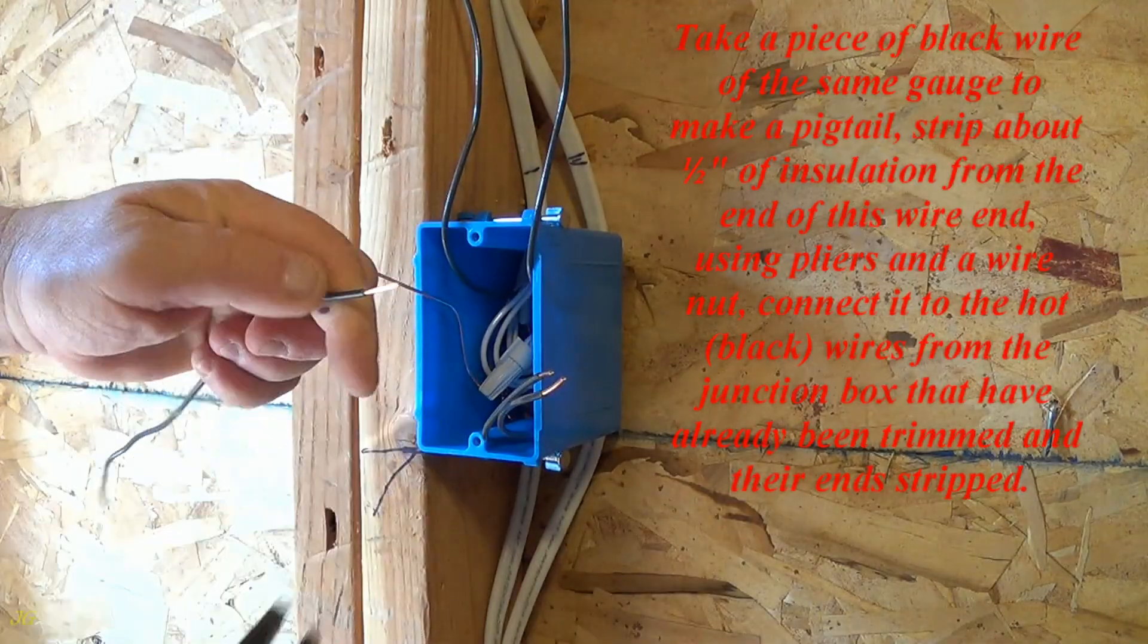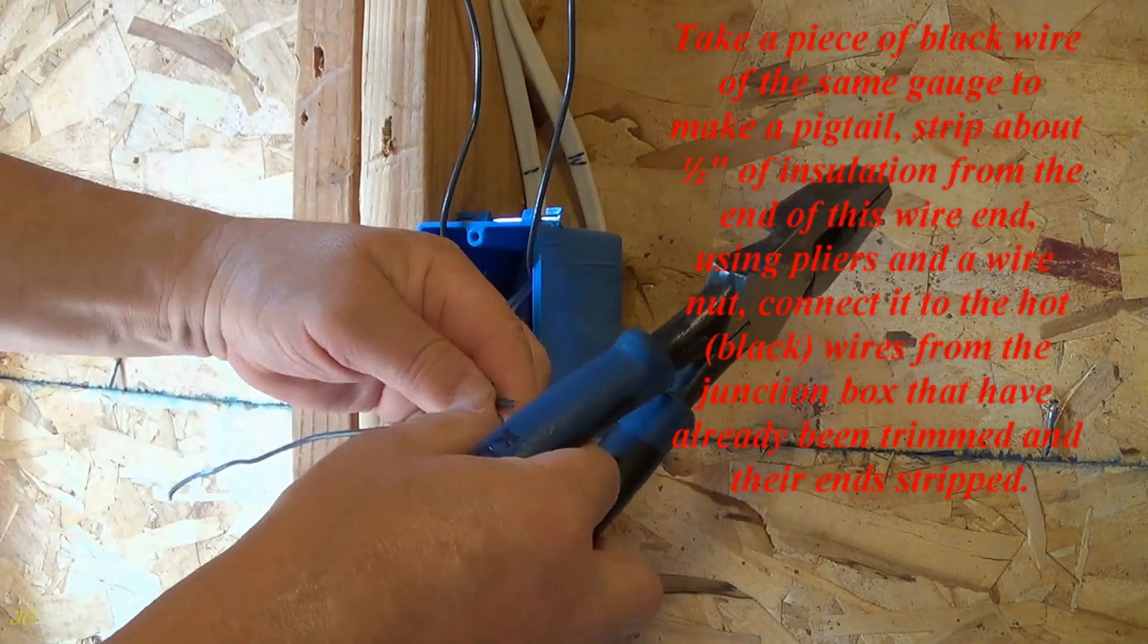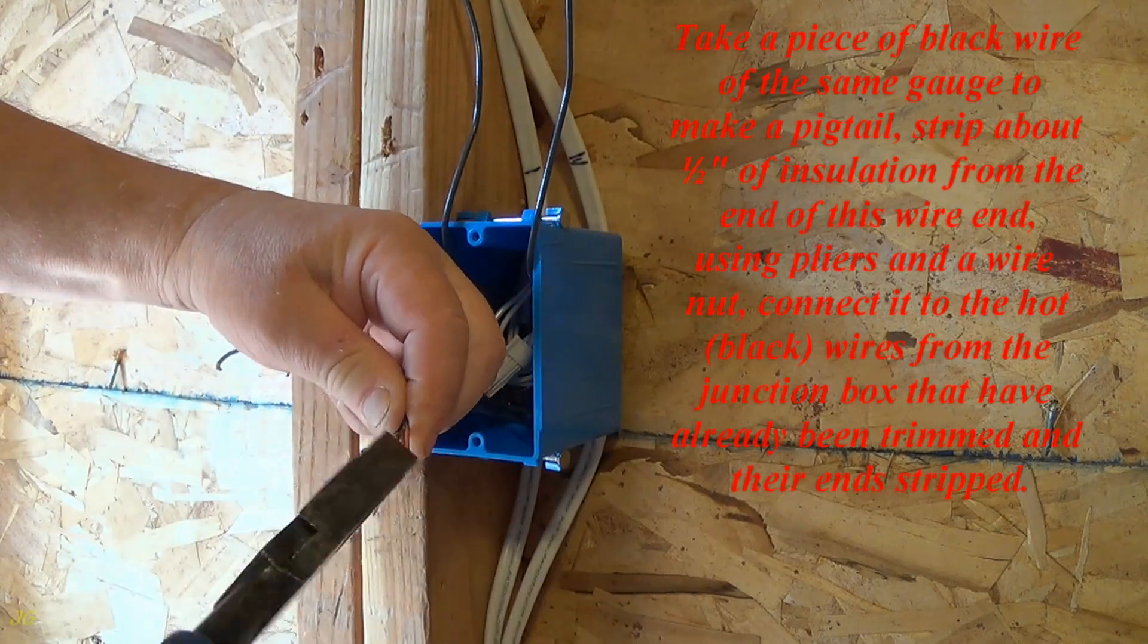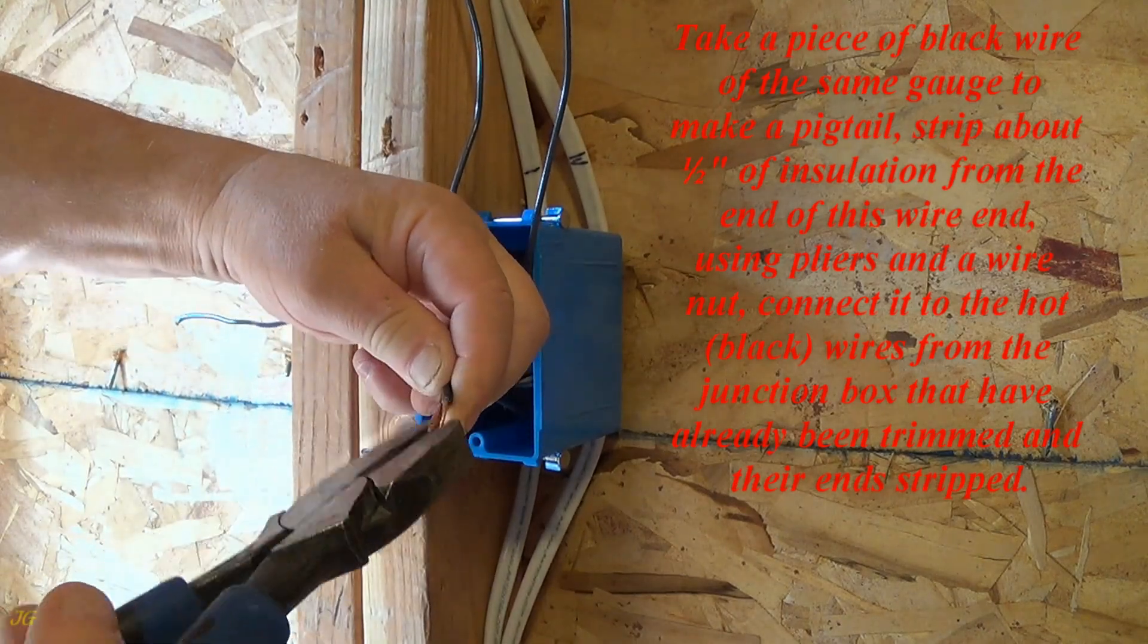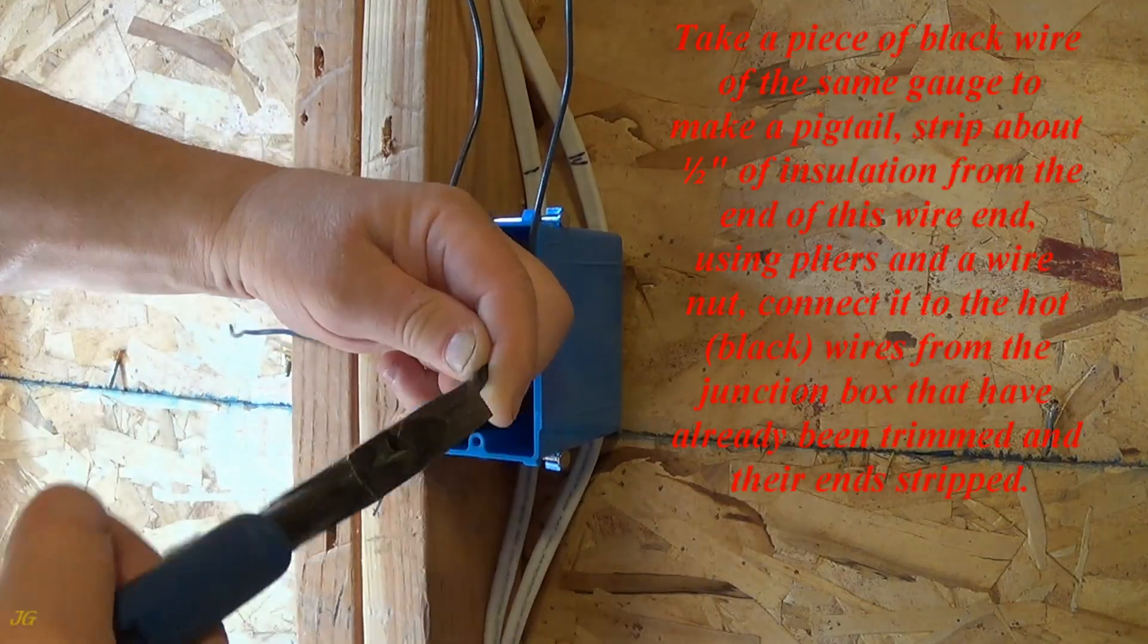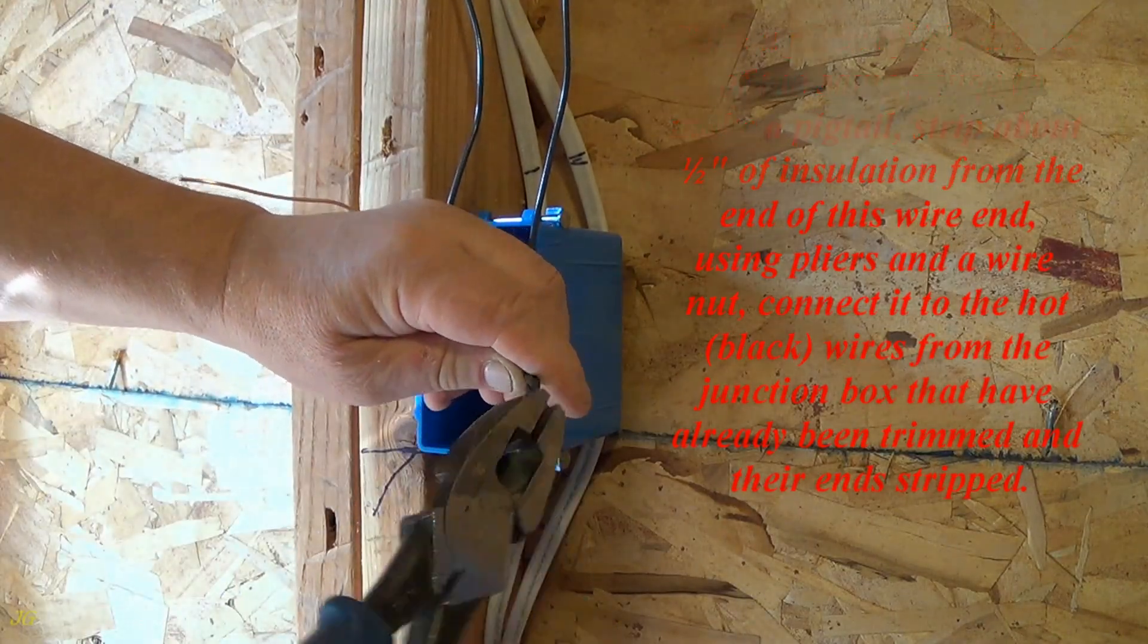Take a piece of black wire of the same gauge to make a pigtail, strip about one half inch of insulation from the end of this wire. Using pliers and a wire nut, connect it to the hot, black wires from the junction box that have already been trimmed and their ends stripped.